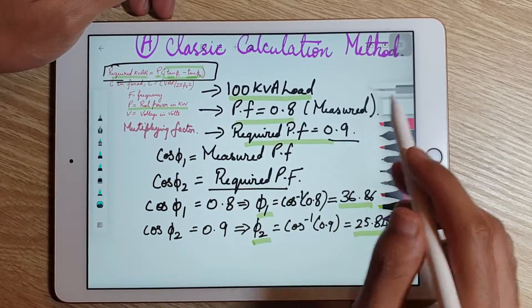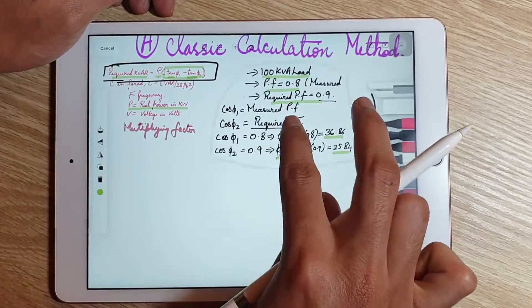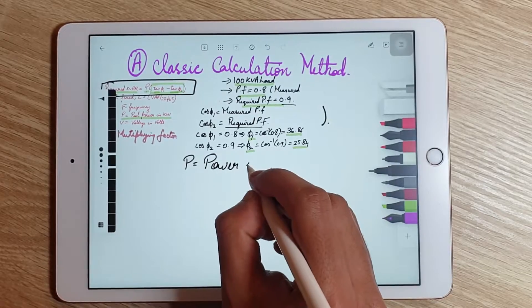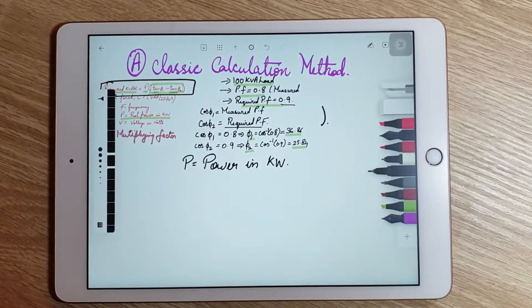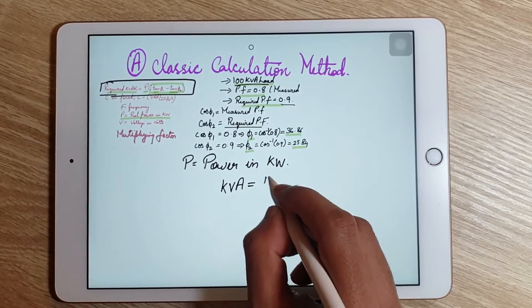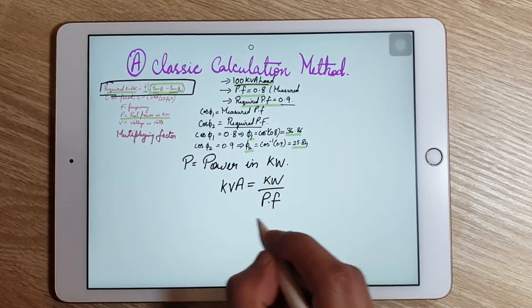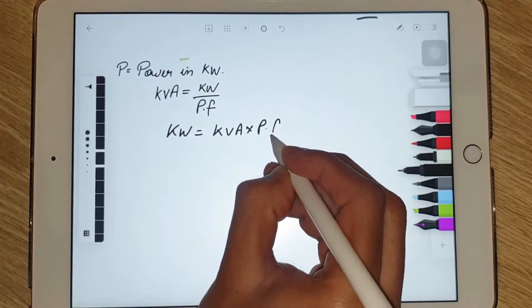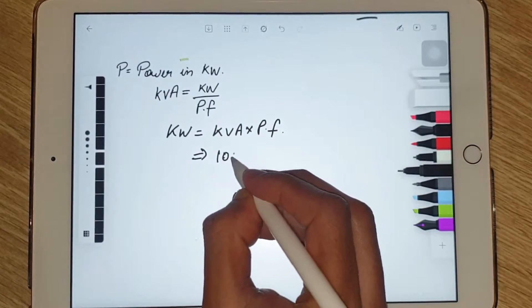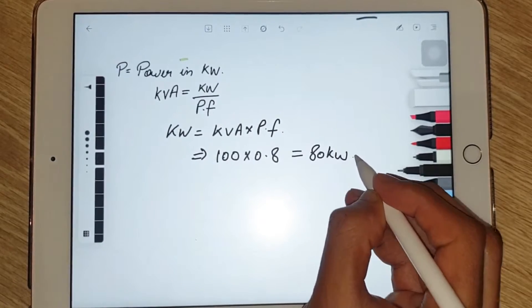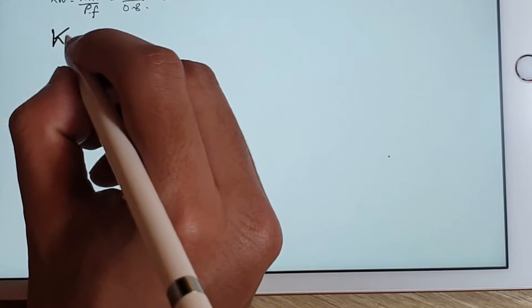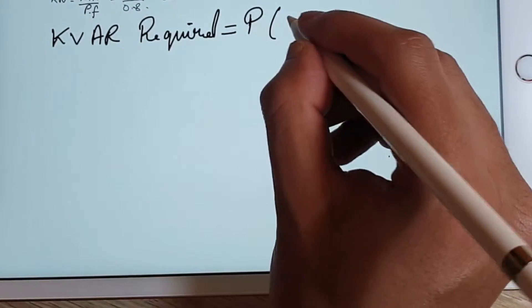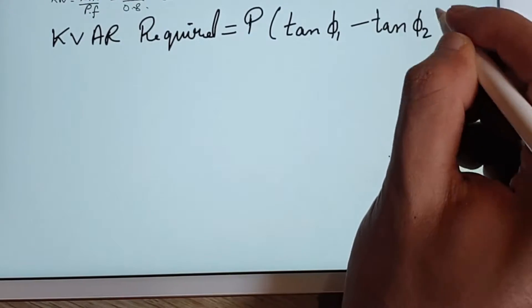We have obtained the values of φ1 and φ2 to substitute into the required KVAR formula. The power value substituted in the formula must be in kilowatts. To convert KVA to kilowatts: kilowatts = KVA × power factor. With a power factor of 0.8, kilowatts = 100 × 0.8 = 80 kW.